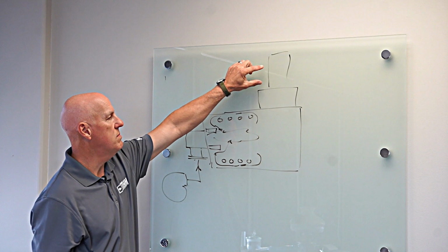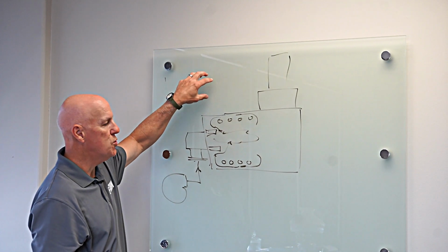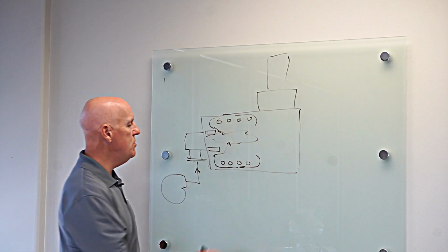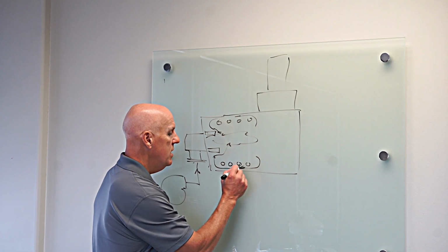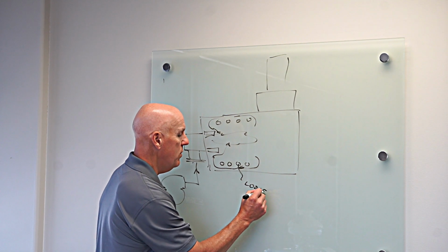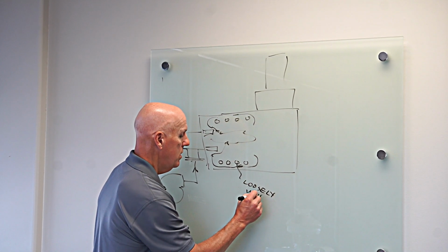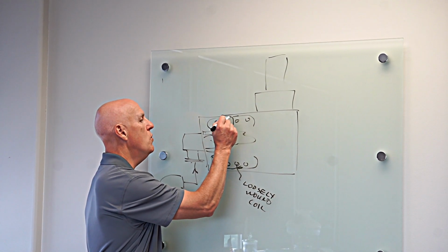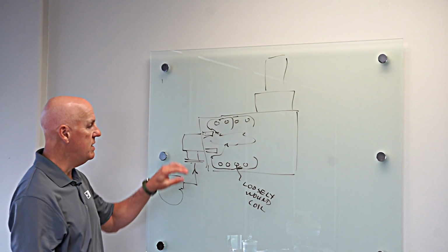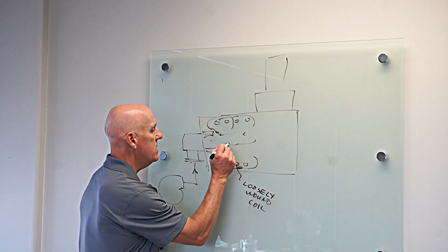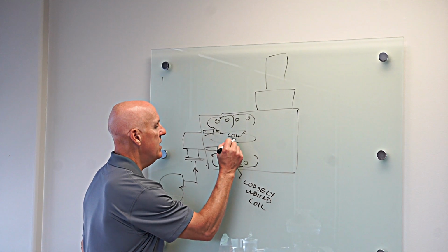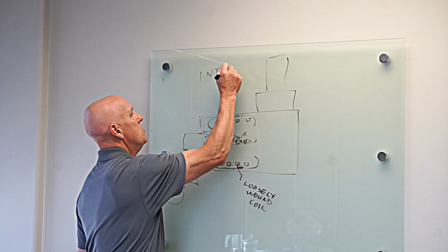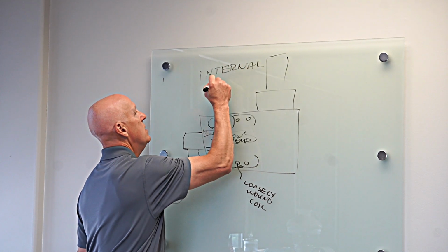So instead of bringing it back externally out of the stack, you do it internally here. I don't have all these problems with condensation, with controls, with a special blower. I've got just a regular blower, but you have to do this with a heater that has a loosely wound coil. Because I have to have space in between these coils for the flue gas to pass, to get back, to be injected into the root and get my low temp flame again, okay? This is called internal flue gas recirculation as opposed to external.